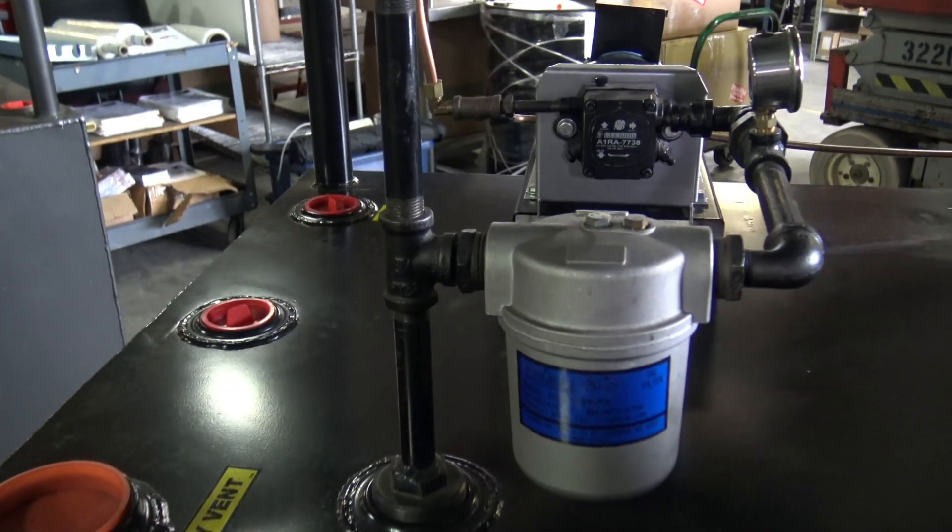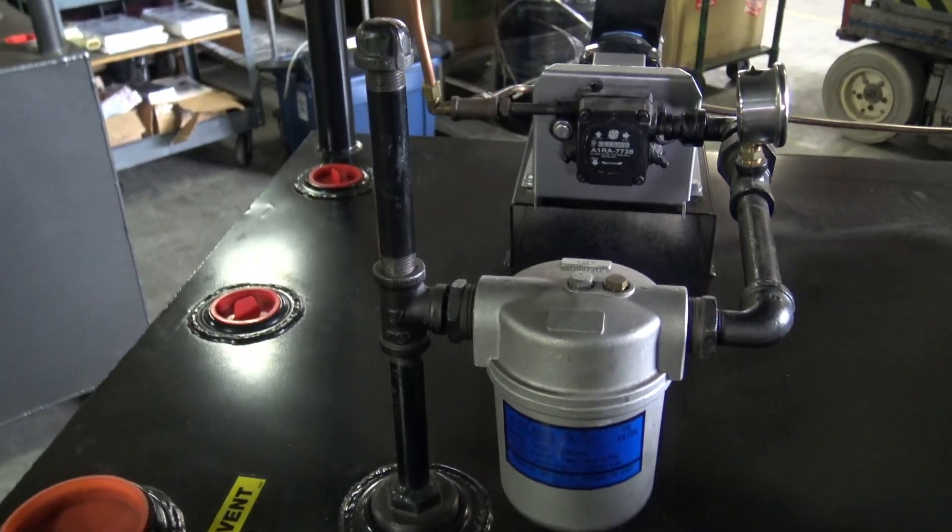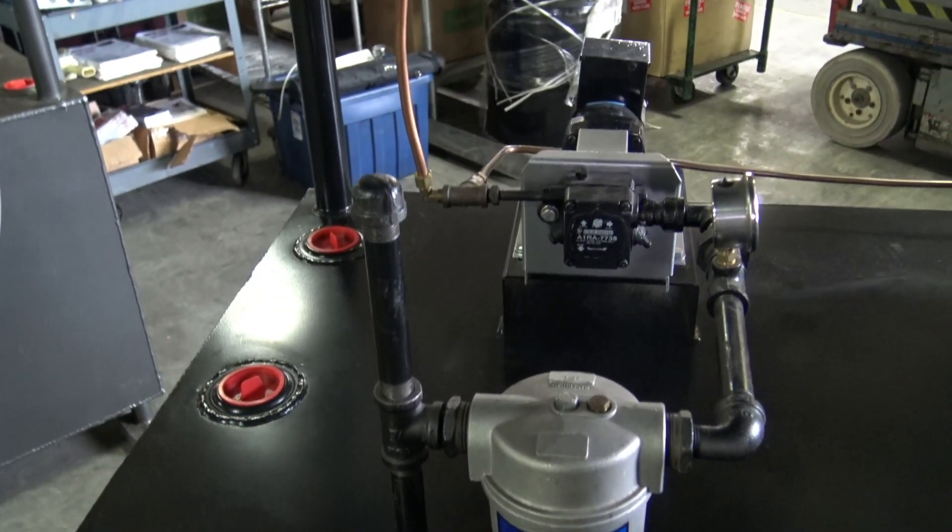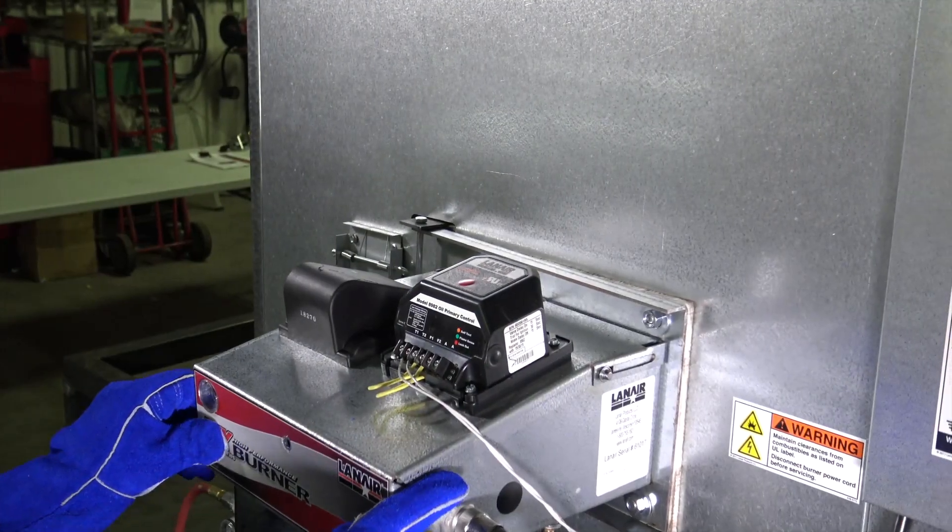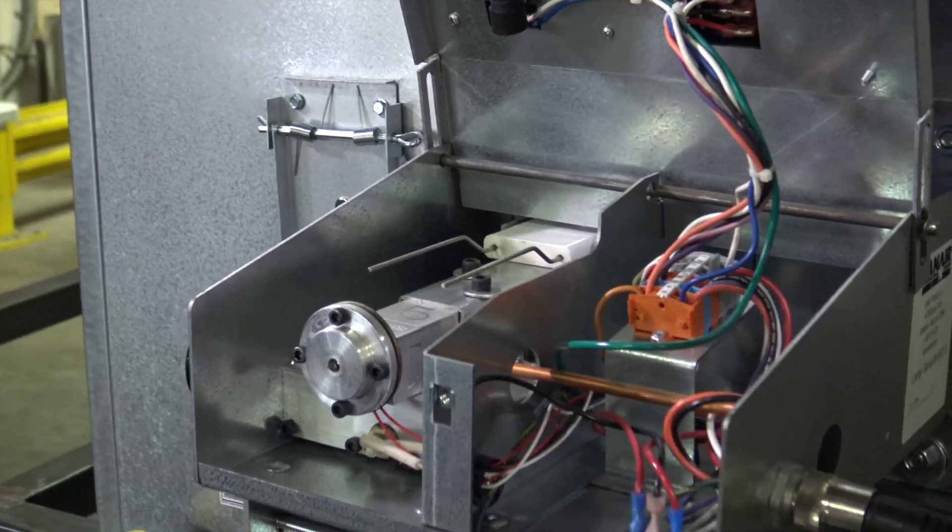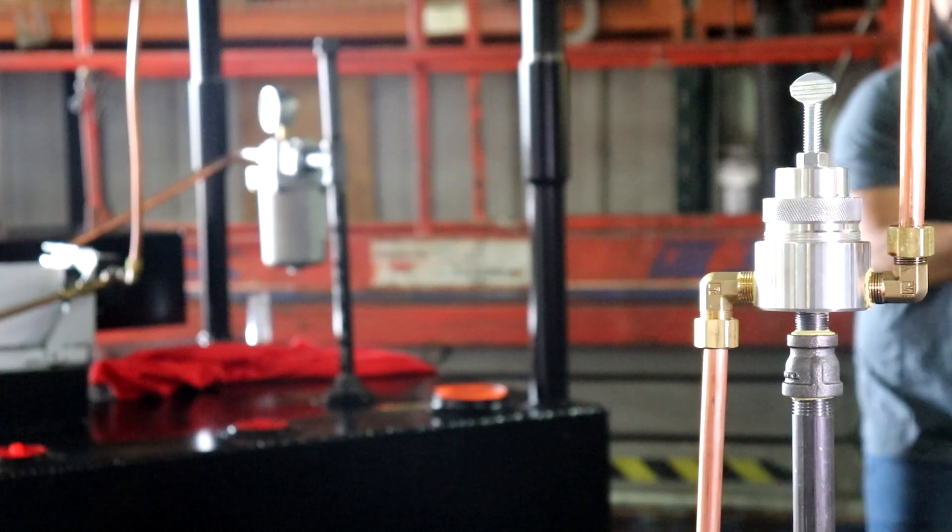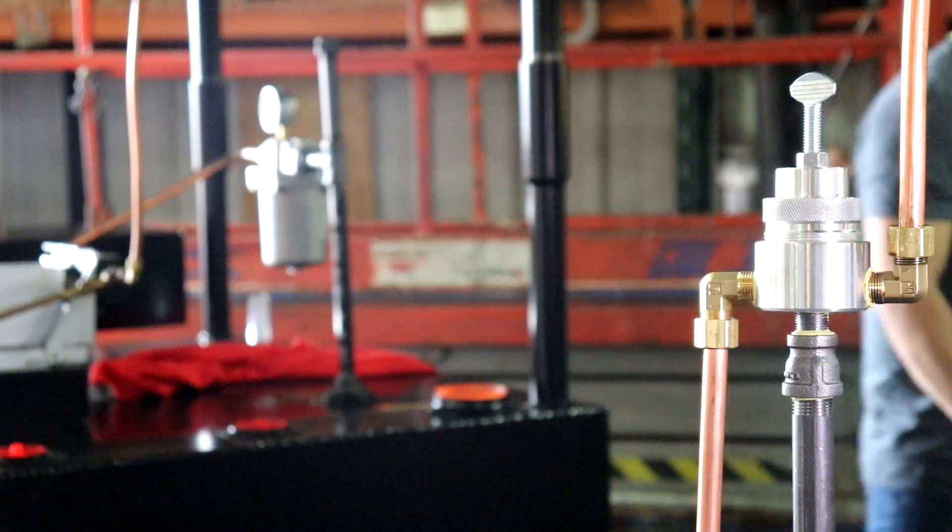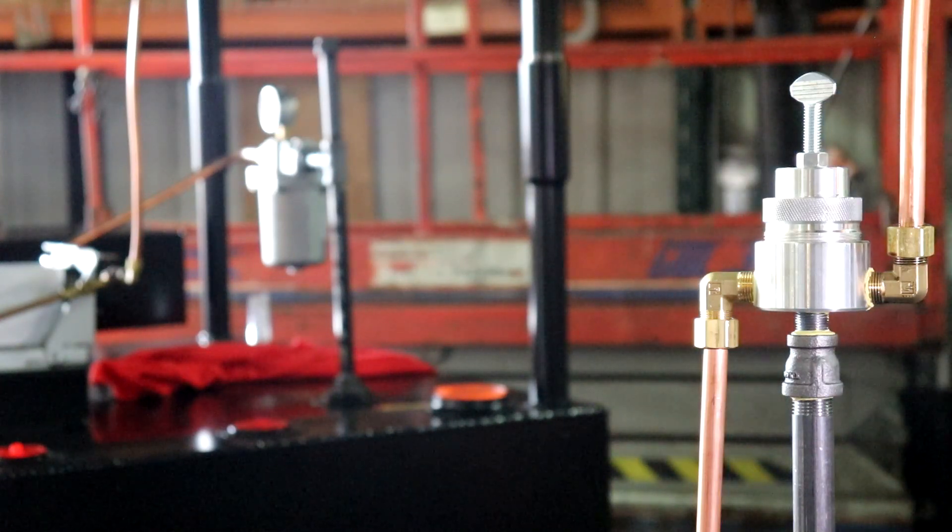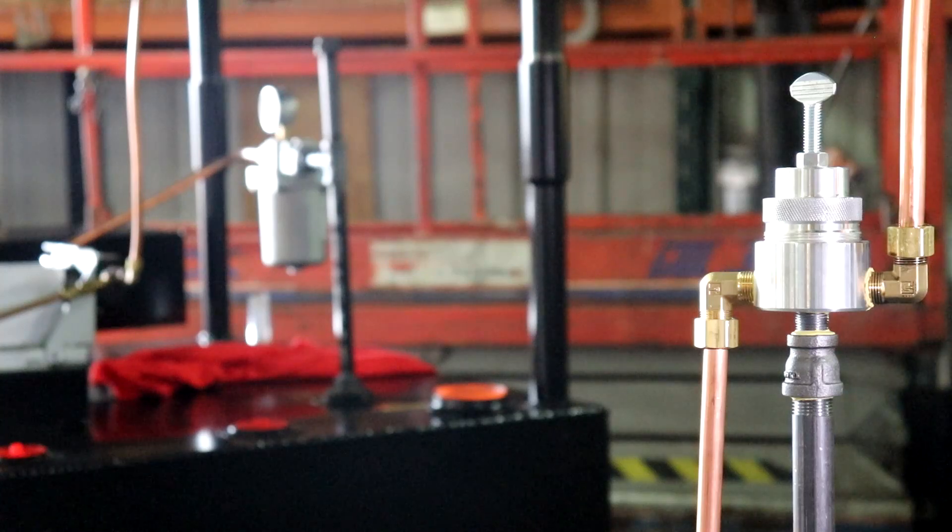Another underlying cause of poor flame quality is often that the fuel is too cold. Maintain a fuel temperature of at least 50 degrees Fahrenheit and periodically check the preheater inside the burner to ensure that it is warm to the touch and functioning correctly. If the temperature of the fuel storage area is allowed to drop too low, it can take a long time for the fuel to warm back up. In freezing conditions, any water that may have settled in the tank will freeze and begin to float back up into the fuel, carrying debris and other contaminants with it, potentially leading to additional issues.